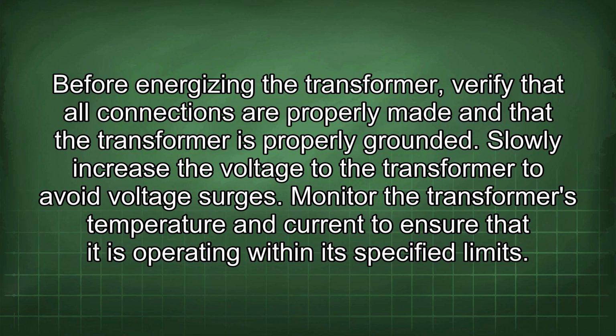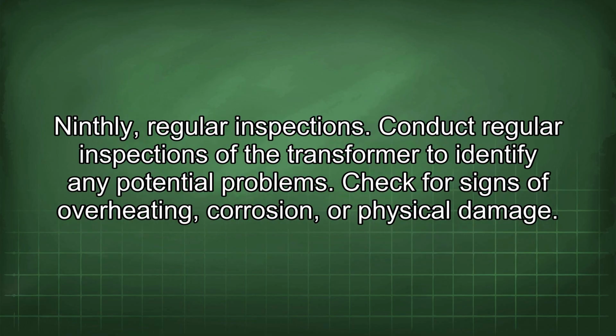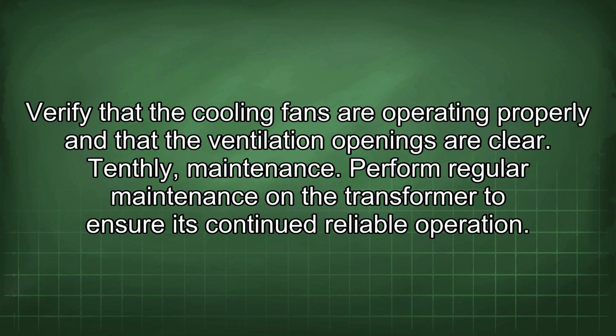Monitor the transformer's temperature and current to ensure that it is operating within its specified limits. Ninthly, regular inspections. Conduct regular inspections of the transformer to identify any potential problems. Check for signs of overheating, corrosion, or physical damage. Verify that the cooling fans are operating properly and that the ventilation openings are clear.